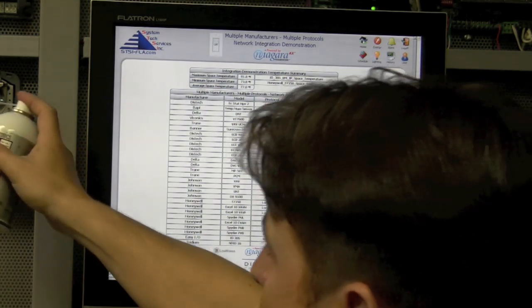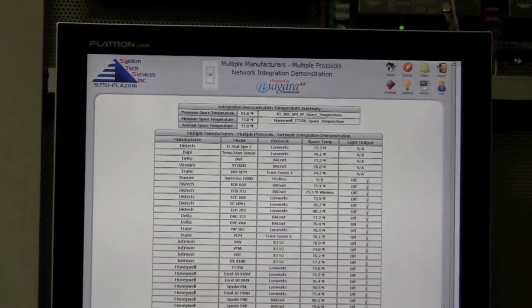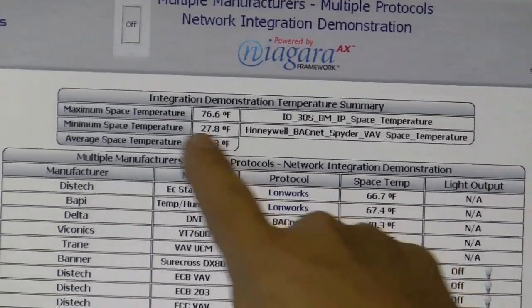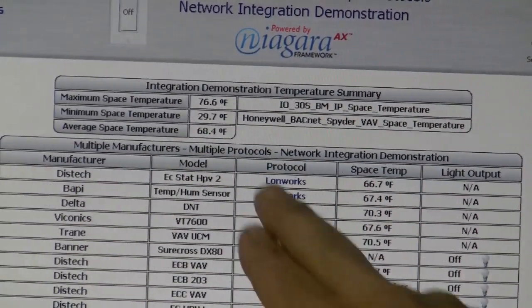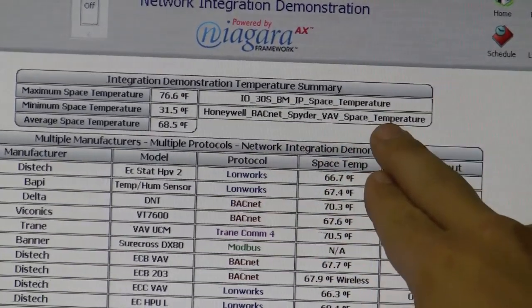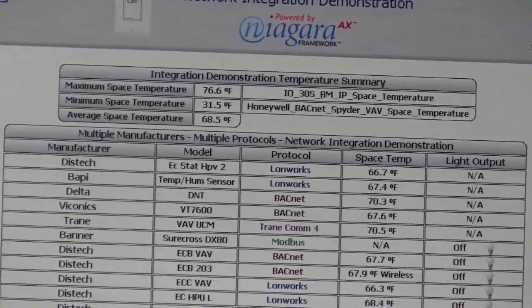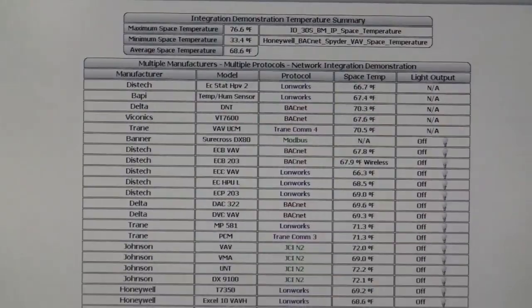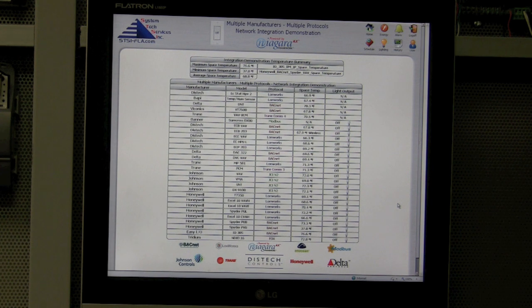In this demonstration I've got maybe 15 or 20 different space temps and some freeze spray. I'll spray this sensor — not only will I show you the minimum space temp on this whole board, but I'll call out who it is. We see 27 degrees is our minimum space temperature. But that information alone doesn't tell you a lot — we tell you exactly where it's coming from. It's coming from a Honeywell BACnet Spyder VAV. We also do set point deviations — it's relative based on set point. We calculate space temperature versus set point and come up with an error, then tell you your worst errors.